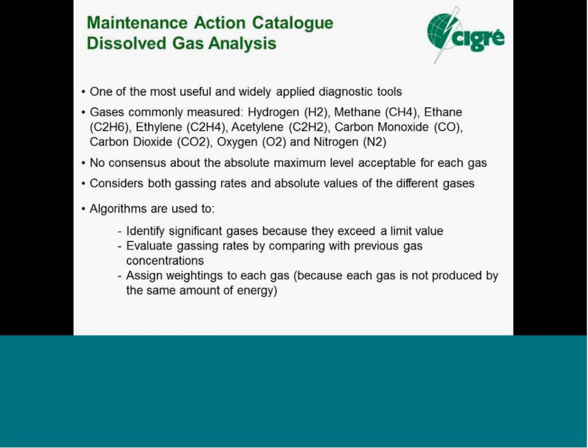Dissolved gas analysis. I encourage you to go to that section and read the further reading, interpretation of dissolved gas analysis. I think each and every one of you involved in our transformers needs to learn about incipient faults, gassing in transformers, and how to interpret the gases that are detected in the oil of an oil sample. You need to look at these interpretation standards.